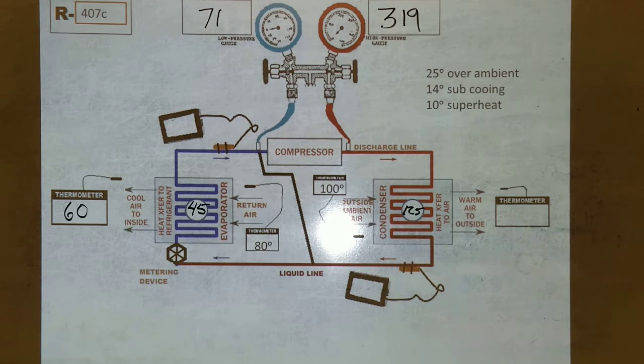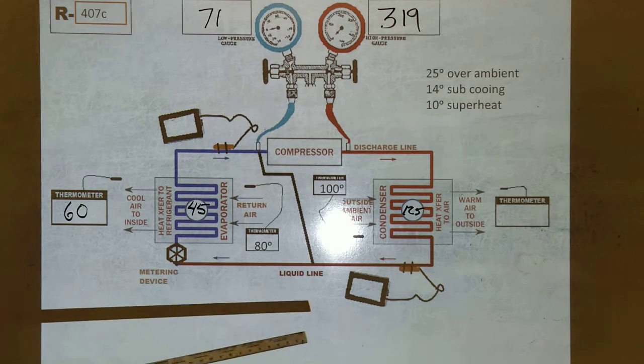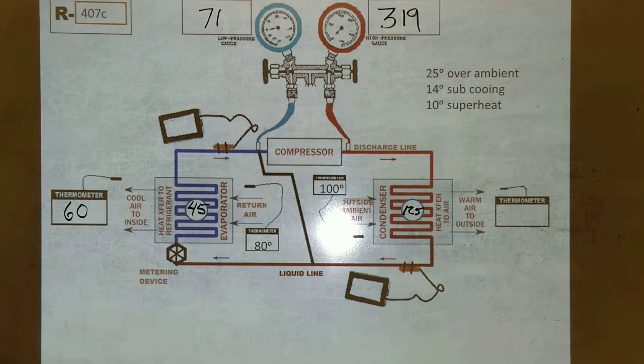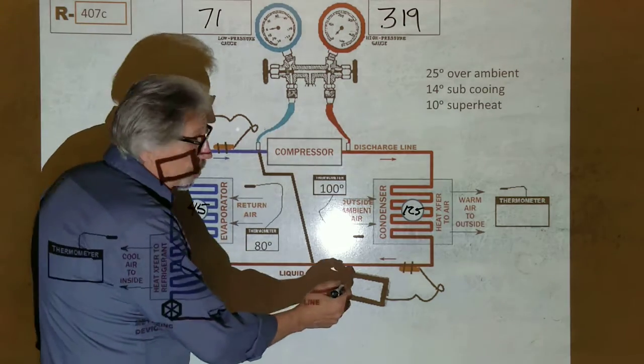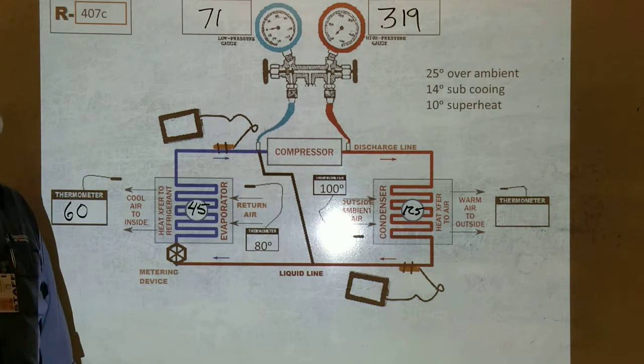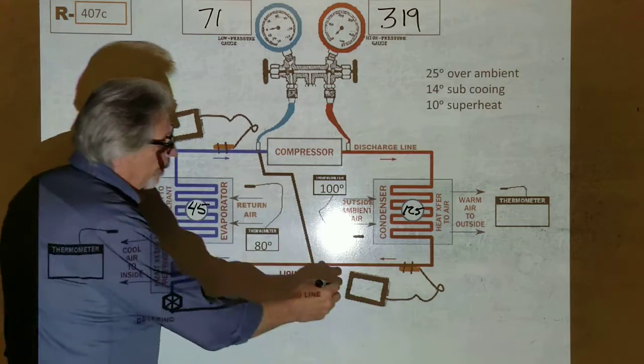Okay, what's our vapor pressure for 45? 71. What's our liquid pressure for 125? 319. Okay, we're using the right charts. If we're looking at 14 degrees subcooling, what temperature are we looking at on our thermometer down here on our liquid line? 111. I got 111. I concur. Okay, sold.